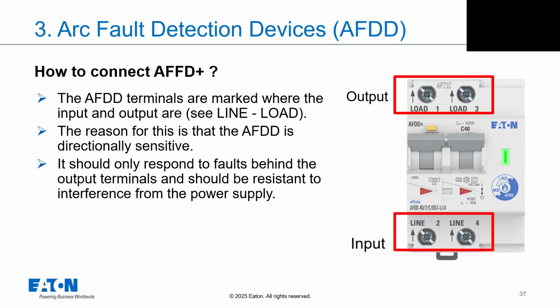And now a very important topic, as was mentioned on previous slides, directional sensitivity. Each AFDD has a very strictly designed input and output. This is mainly for installers: it's not like an MCB or RCD where you can swap input and output. No, here it's not allowed. The installer must follow very clearly what is incoming and what is outgoing, and then the device will work properly. And then very important information: input and output must be clearly specified in the installation.